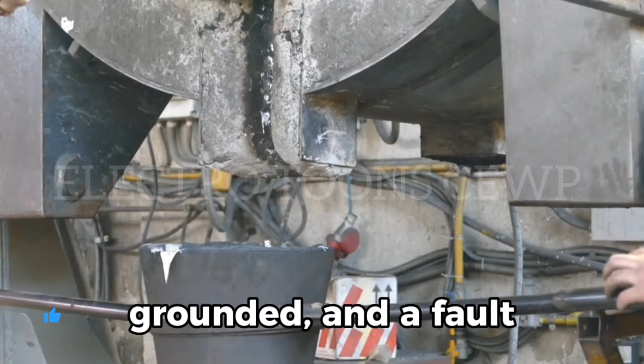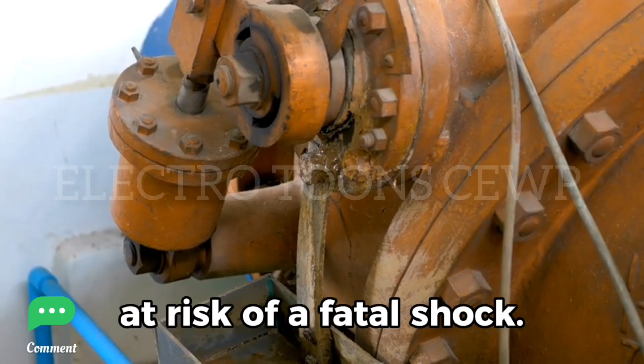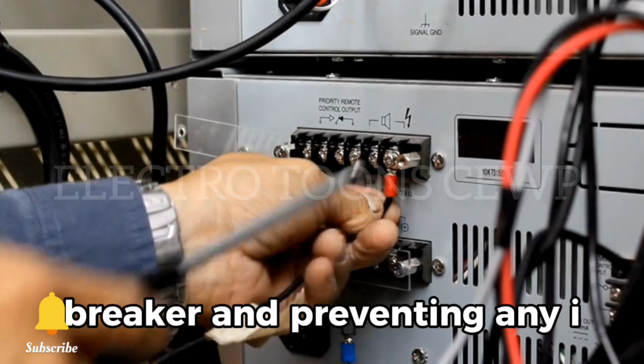Real-life example. In an industrial setting, if the metal casing of a machine is not properly grounded and a fault occurs, it could lead to the casing becoming energized, putting workers at risk of a fatal shock. Proper grounding would ensure the fault current flows safely to the earth, triggering the breaker and preventing any injury.